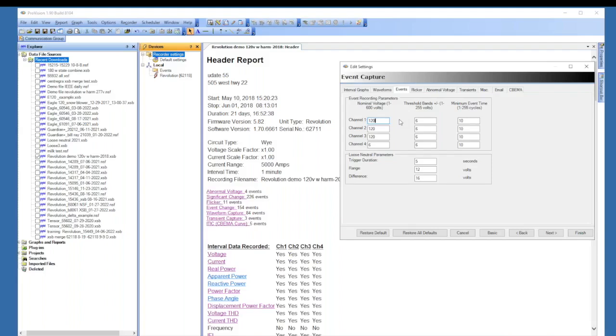And when you look at just the voltage graph, you'll see, like I said, the highest cycle and the lowest cycle during that interval. But it's not going to tell you on the lowest cycle how many cycles it was down that low. So that's where the event capture comes in. So if you look at your event capture, it will tell you when it went outside of those trigger ranges, which channel was outside, how many cycles it stayed outside of that trigger range, voltage range, and what the current is, min and max during that event, before the event, after the event. So you can see if inrush caused the voltage to drop, or possibly a motor turning off caused the voltage to rise. So this is a good one to get correct.